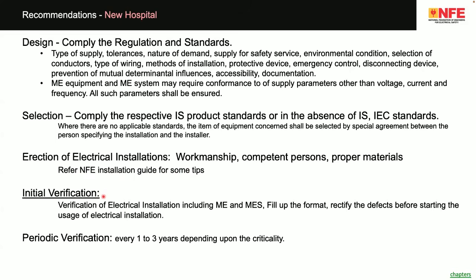Initial verification, I would say very, very important. Please note that the initial verification has to be carried out by a third party, meaning the consultant as well as the contractor should not be involved in verification. This has to be by a third party, because only then can the mistakes be identified, termination problems, cable routing problems, glanding problems, and you can rectify everything. Verification of electrical installation, including medical electrical and medical electrical system. Now you have the formats, you fill up the format, and rectify the defects before starting the usage of the electrical installation.